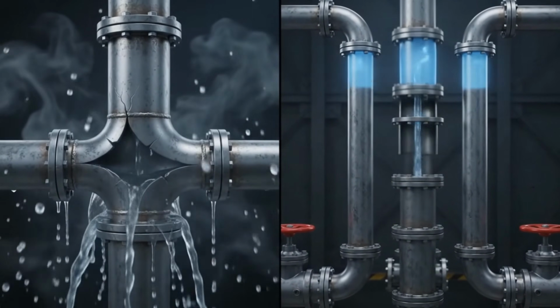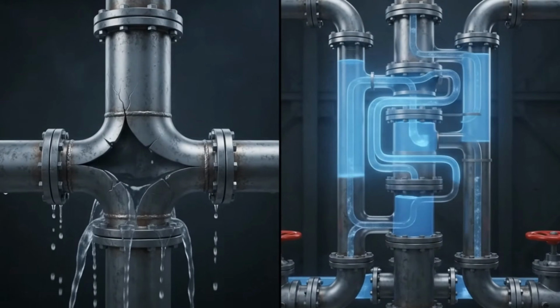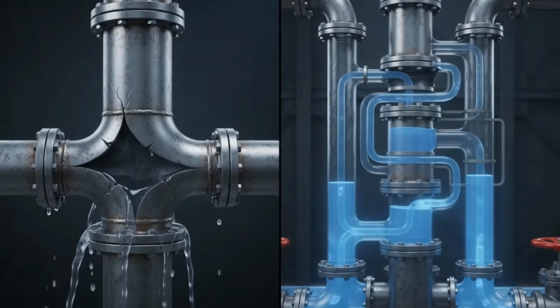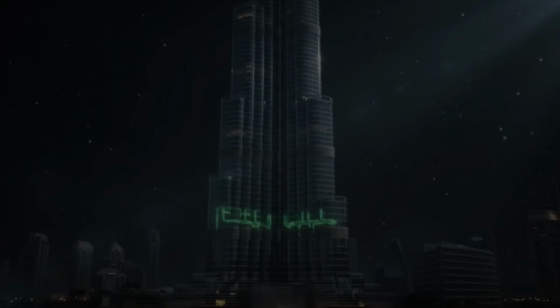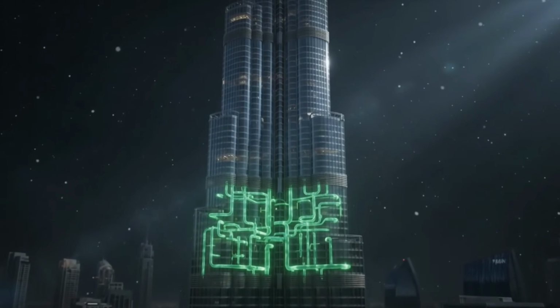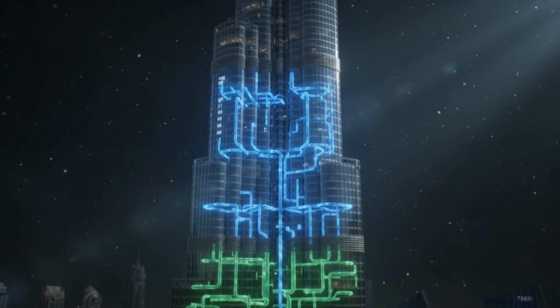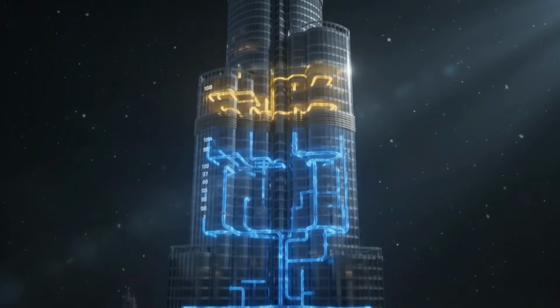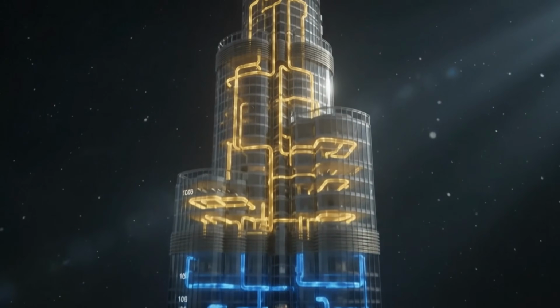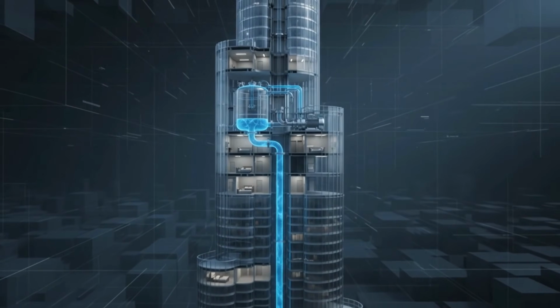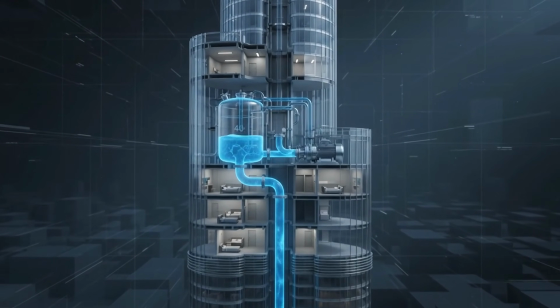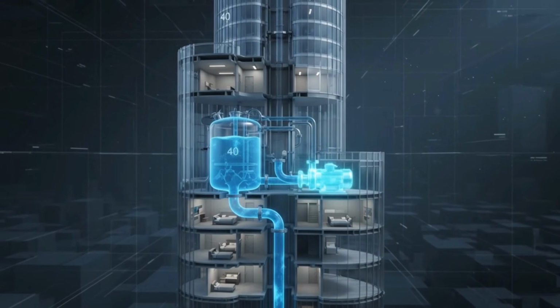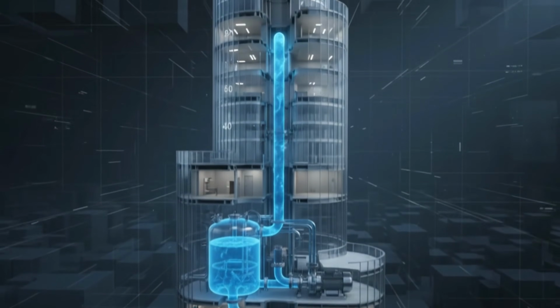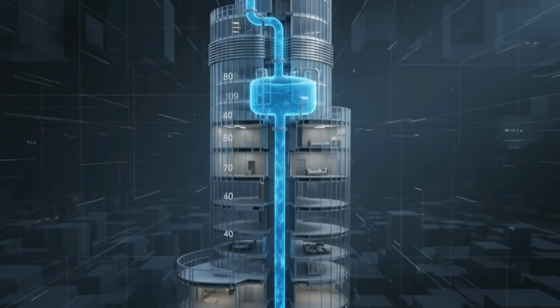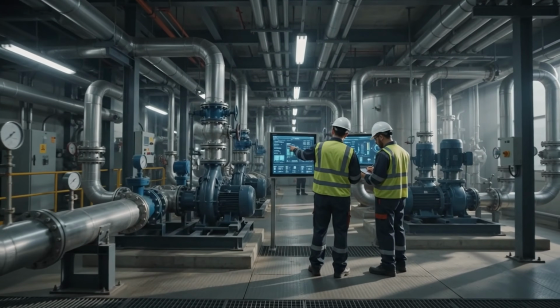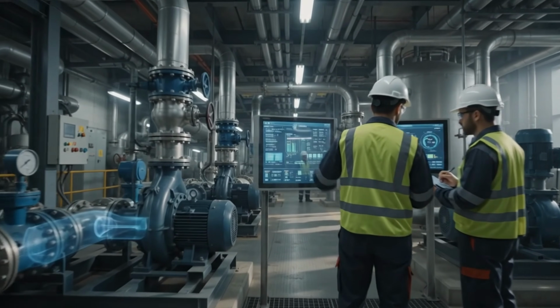The engineer's solution was elegant. Divide the building into vertical pressure zones, each managing only its own section of pressure. Divide and conquer. The tower is divided into 3 primary pressure zones. Zone 1 covers the lower floors. Zone 2 handles the midsection. Zone 3 reaches all the way to the summit. The relay approach works like climbing a mountain in stages, setting up base camps along the way. Rather than attempting the summit in one impossible leap, the mechanical floors are where the real engineering lives.